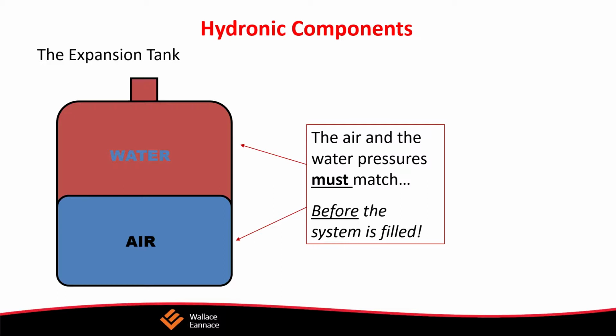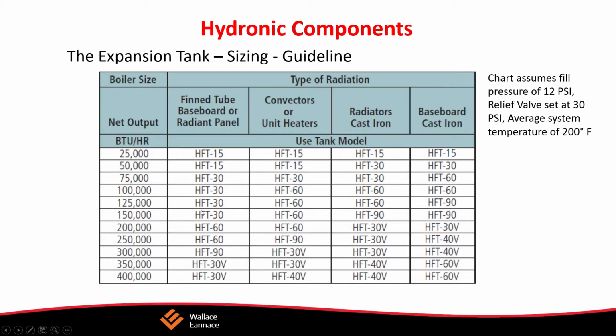This is so pronounced that on the residential boilers, Lochinvar has now integrated a variable speed pump that's controllable as standard equipment. Now on commercial boilers, they don't provide a pump because they really don't know what your delta T's are, what your flows are going to be. Those need to be selected, which once again, we're here at Wallace Eannace, we're happy to help you with that selection.